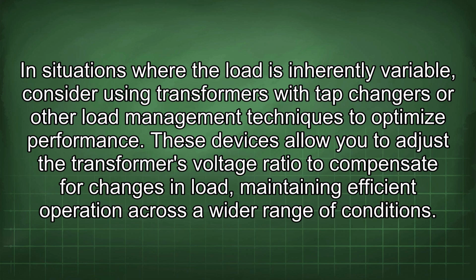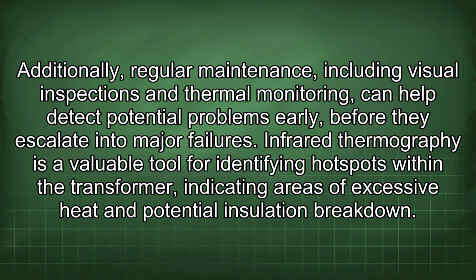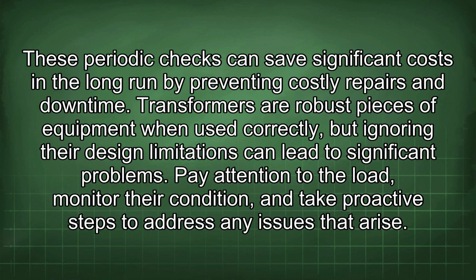These devices allow you to adjust the transformer's voltage ratio to compensate for changes in load, maintaining efficient operation across a wider range of conditions. Additionally, regular maintenance, including visual inspections and thermal monitoring, can help detect potential problems early before they escalate into major failures. Infrared thermography is a valuable tool for identifying hotspots within the transformer, indicating areas of excessive heat and potential insulation breakdown. These periodic checks can save significant costs in the long run by preventing costly repairs and downtime. Transformers are robust pieces of equipment when used correctly, but ignoring their design limitations can lead to significant problems.